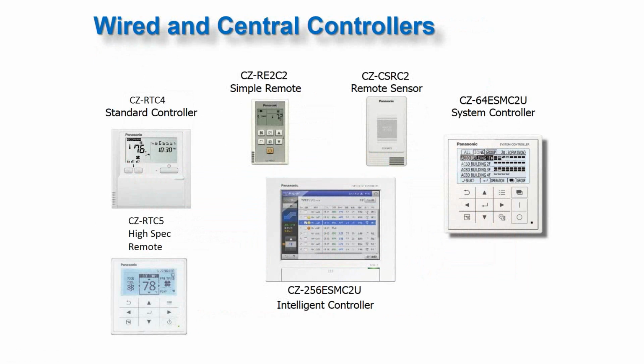These are our control options for our indoor units or our system controls. The most standard, most popular controller is the CZRTC4. This is the standard programmable wall-mounted thermostat. This is a wired option. This is basically the same thing, like the 2.0 version of the standard. This is the CZRTC5. This is the high-spec remote. You can do programming with this. You could also do troubleshooting. You can have access to error codes if you need to do service.